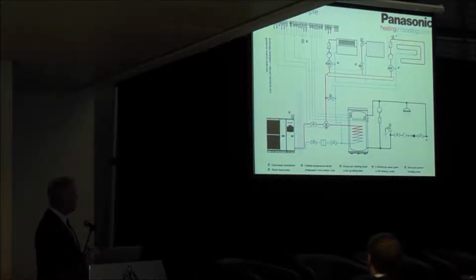There are two set points programmed into the heat pump, one for the domestic hot water and one for the heating cycle. In the cycles which are programmed when you commission the system, you decide what your set point in your tank is and what your set point in your heating system is. Weather compensation is built in on the heating side, not on the domestic hot water side. The domestic hot water temperature has to be constant. So weather compensation is built in on the heating side, so depending on the ambient temperature, you can shift the design flow temperature, the calculated flow temperature, to your heating system.